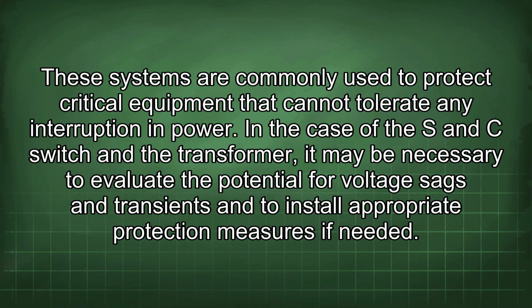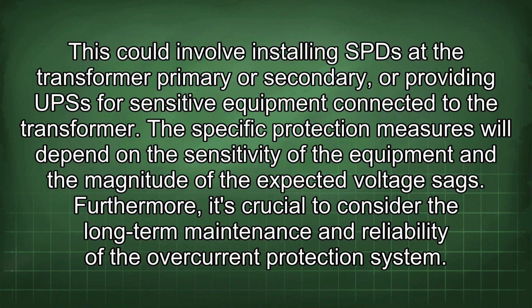In the case of the S and C switch and the transformer, it may be necessary to evaluate the potential for voltage sags and transients and to install appropriate protection measures if needed. This could involve installing SPDs at the transformer primary or secondary, or providing UPSs for sensitive equipment connected to the transformer. The specific protection measures will depend on the sensitivity of the equipment and the magnitude of the expected voltage sags. Furthermore, it's crucial to consider the long-term maintenance and reliability of the overcurrent protection system.